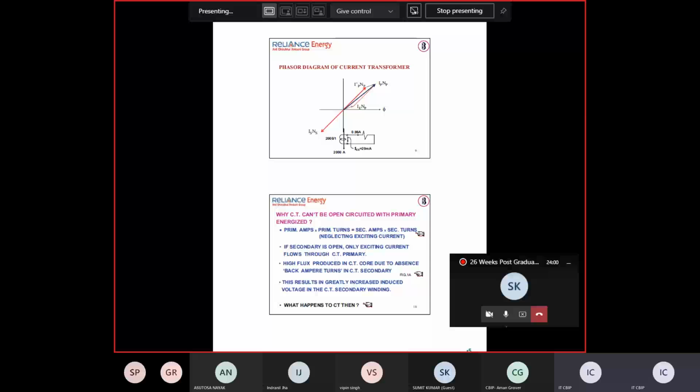It is very simple. Instead of 2000, I have asked, what will it be? Anybody please? For 66 kV, roughly what will be the current value? Sir, 874 amps. Yeah, correct. Upper 100 MVA transformer. Source, signal here? 100 MVA transformer. No, don't take 100, how can it be 100 at 66 kV? In 66 by 11, the power transformer is 20 or 25 MVA.